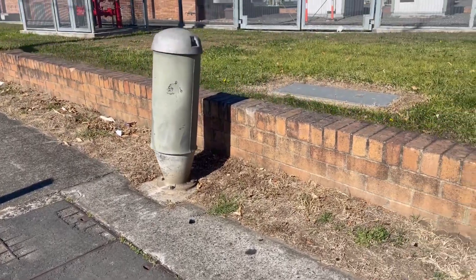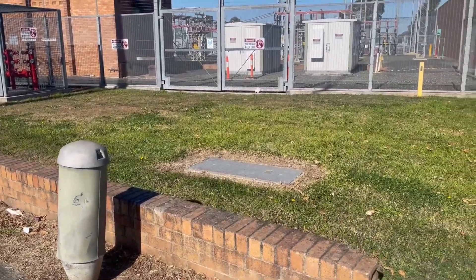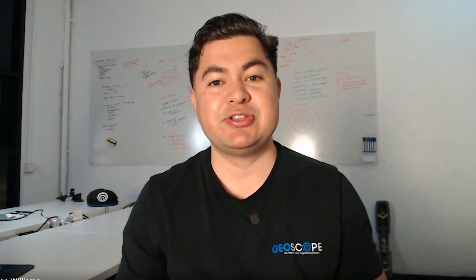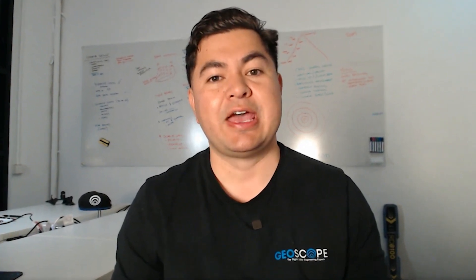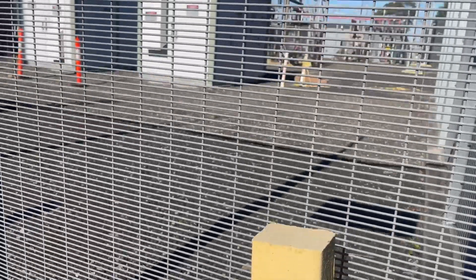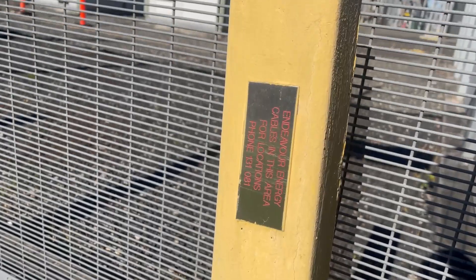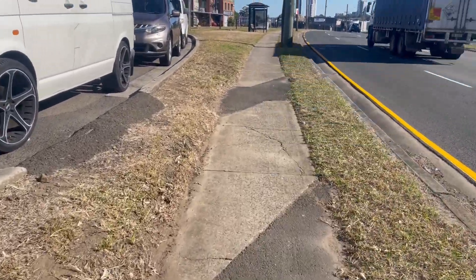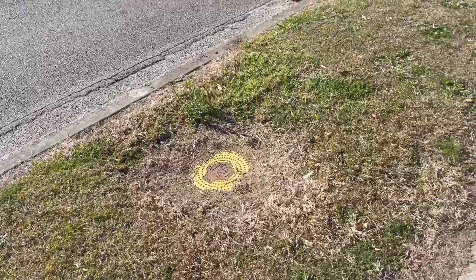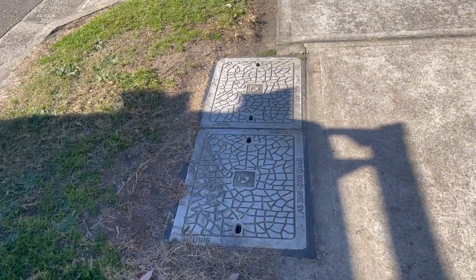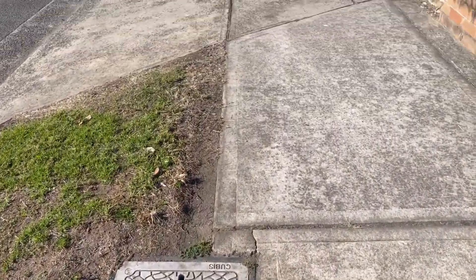There are some other signs of electricity cables in the area that we first need to establish by doing a thorough site walkthrough. As you walk up and down the road there are pits, valves, and hydrants — you need to be aware of what's underground, as some of these utilities can affect the accuracy of passive scanning. During our walkthrough we're noticing signage plaques on the curb, scarring in the road, warning posts, signs of trenching, services going from overhead to underground, and even different patches of grass.